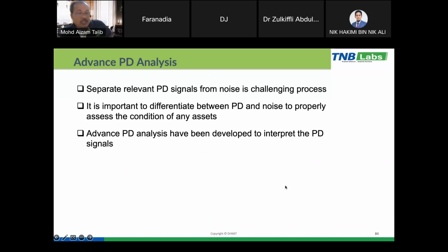Yeah, on the last topic, more on the advanced PD analysis. As I said, the challenge in carrying out PD activity measurement at site is more on the noise or disturbance. So it is quite difficult to separate the PD signal from the noise. So through this advanced PD analysis, we are able to differentiate between the PD and noise.